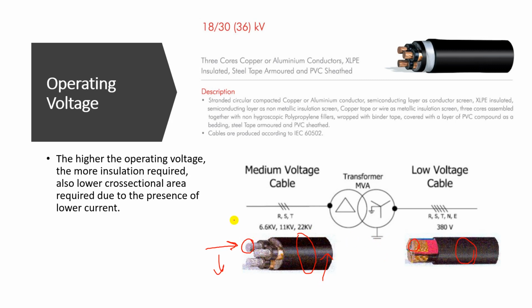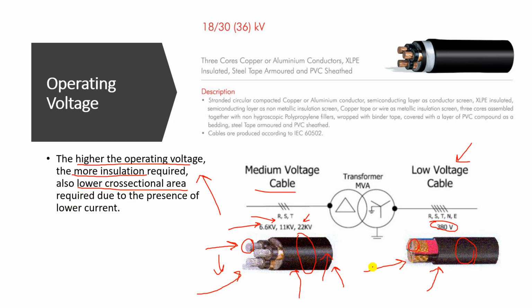Now, why is this? First, the higher the operating voltage, such as 6.6, 11 or 22 kilovolt, which is higher than 380 volt, the more insulation is required. So this black insulation is very large compared to the insulation in the low voltage cable, because this cable operates at a medium voltage. Second, the cross-sectional area of the core is lower in the medium voltage cable due to the lower current in the medium network.